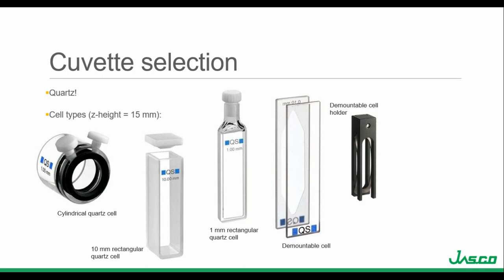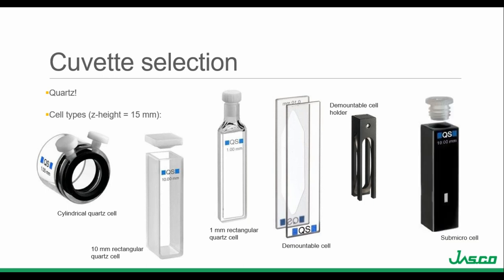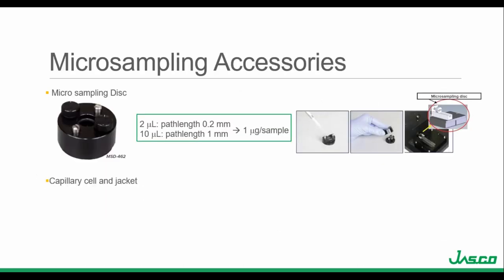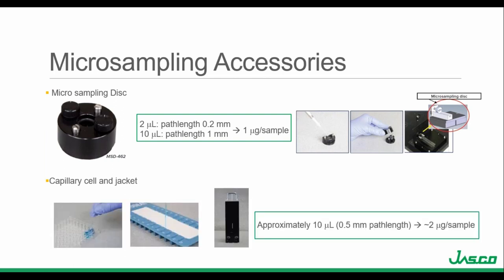The demountable cells also require a demountable cell holder because the two cell plates are sandwiched together and secured in place. It's also important to verify the path length of the demountable cells after loading to ensure the correct path length, especially if calculating molar ellipticity or mean residue molar ellipticity where concentration and path length corrections are needed. Rectangular micro and submicro cells are also available for small volume measurements in a variety of volumes and path lengths. These cells have smaller apertures, so it's important to use a black mask cell if the cell window is smaller than the instrument beam.